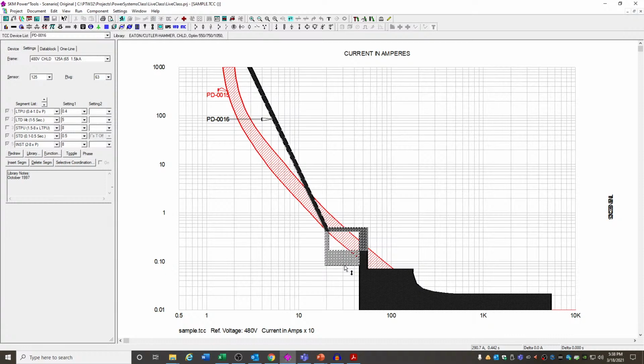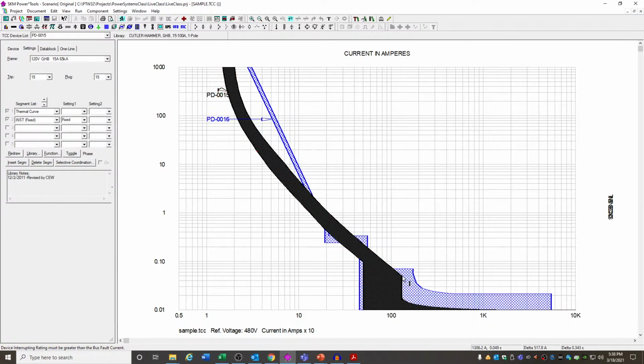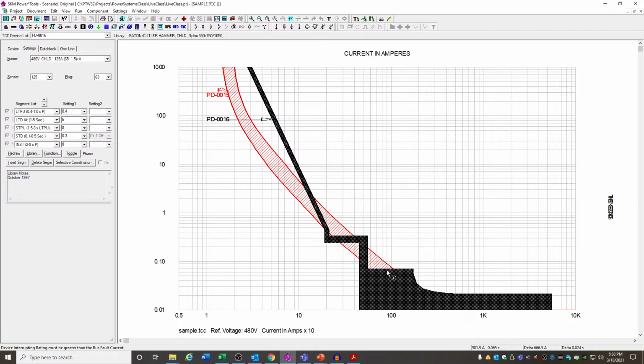So when I'm moving, look, I'm adjusting this. What am I doing? I'm adding an intentional delay. This is not the instantaneous region. This over here in this black all the way over to the right, there is no intentional delay added. This clearing time of 0.01, 0.02, 0.03, 0.04, 0.05, 0.06, 0.07 seconds right here, and then you get into the real fast clearing time.